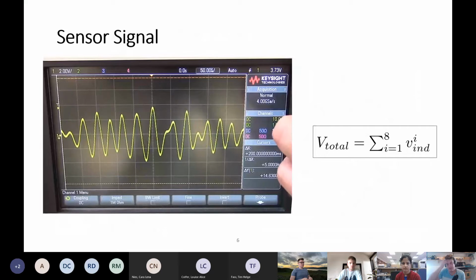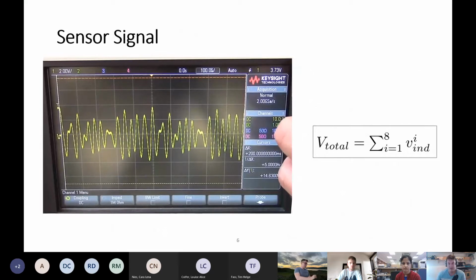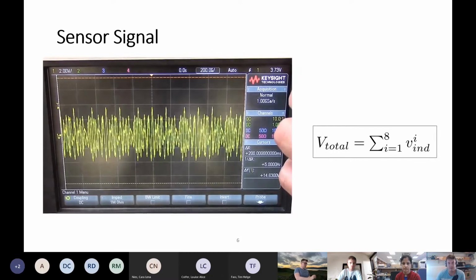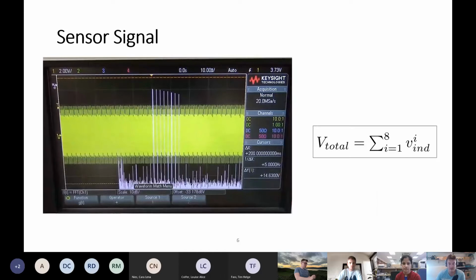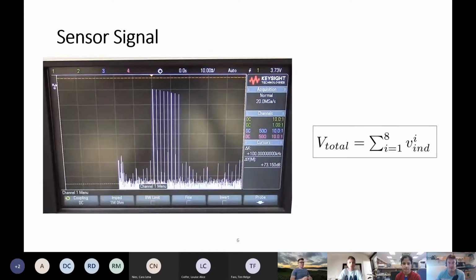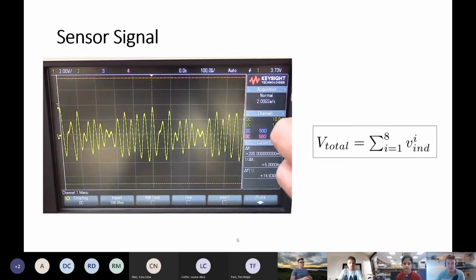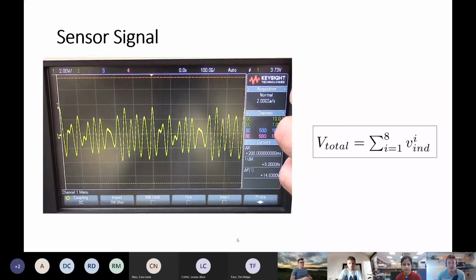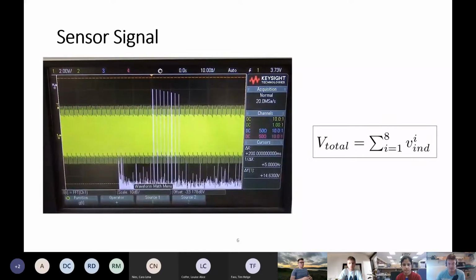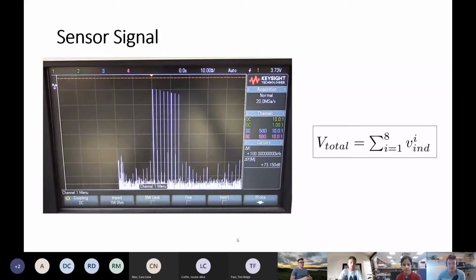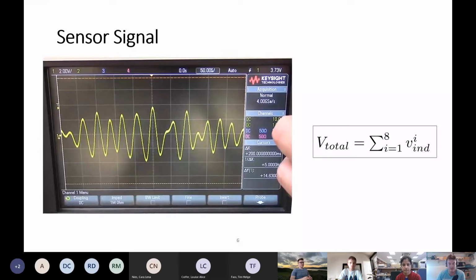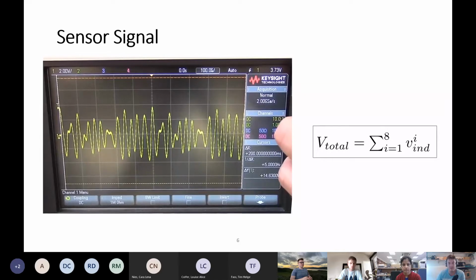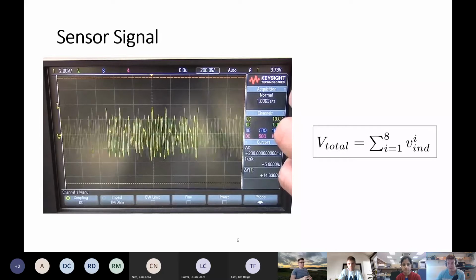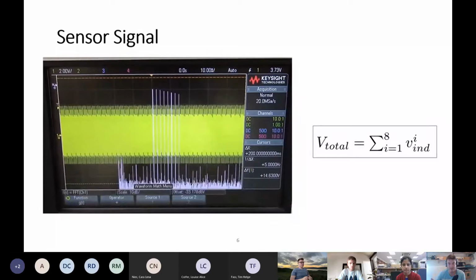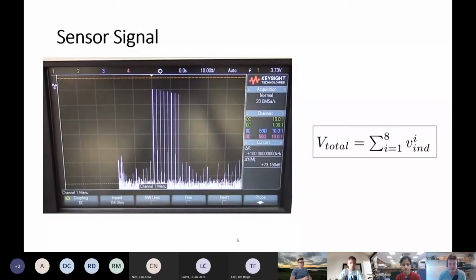This video shows what the signal on the sensor looks like. Each of the coils transmits a sinusoidal frequency in the kilohertz range, and all those magnetic fields get mixed together in the volume above the field generator. So what the sensor sees is essentially a sum of all those sine waves added together—on the scope, that signal looks like a modulated sine wave. But when you take an FFT, or Fourier transform, you can see these 8 purple peaks appear, each corresponding to the frequency, or the magnitude of the frequency, measured at that point.